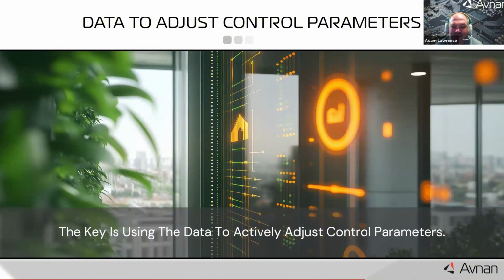The key is using the data to actively adjust control parameters. For example, many variable speed systems use PID control loops. Those loops can have adaptive tuning. The controller can shorten or lengthen compressor cycles based on past oscillations to eliminate overshoot. Or consider multi-stage equipment. A two-stage compressor unit can decide to stay in low stage longer if it sees that it's maintaining set point, thus saving energy and reducing wear.